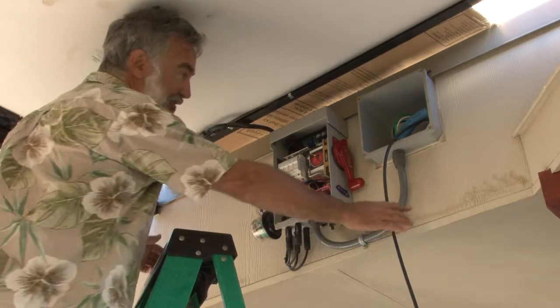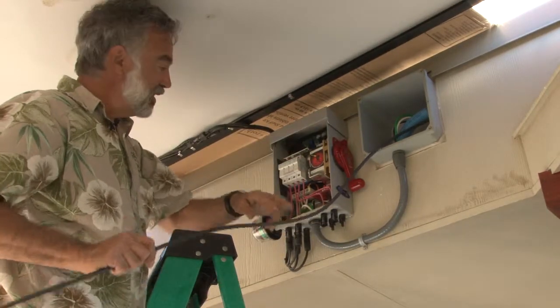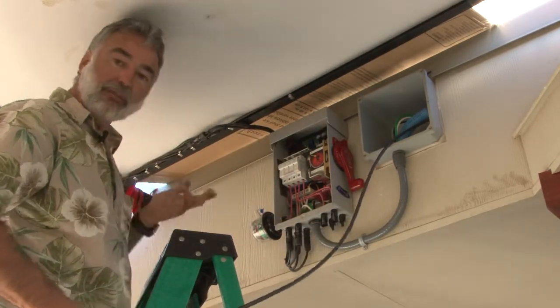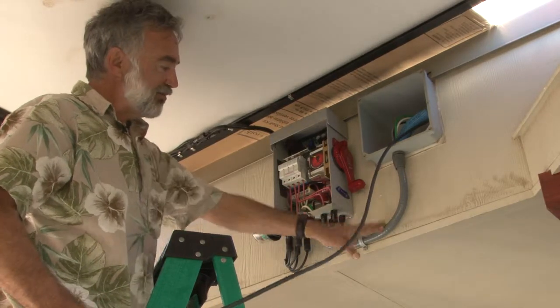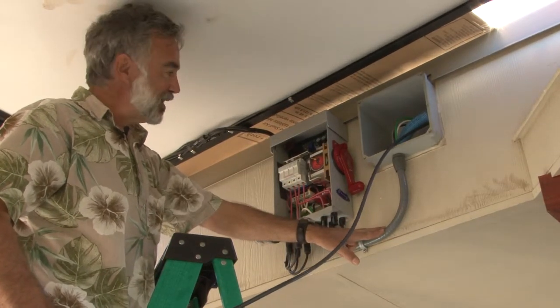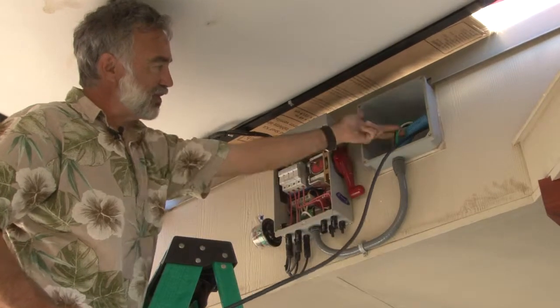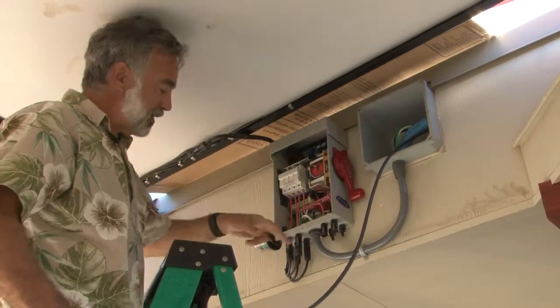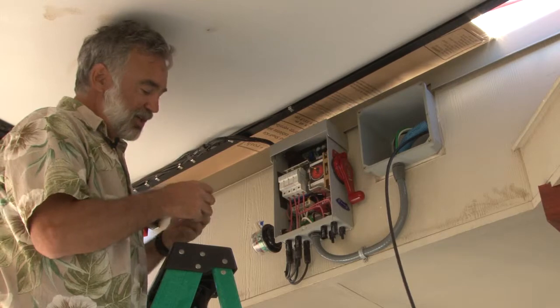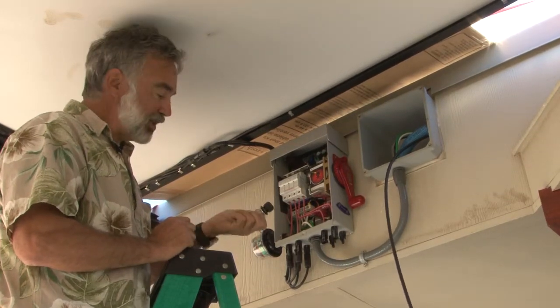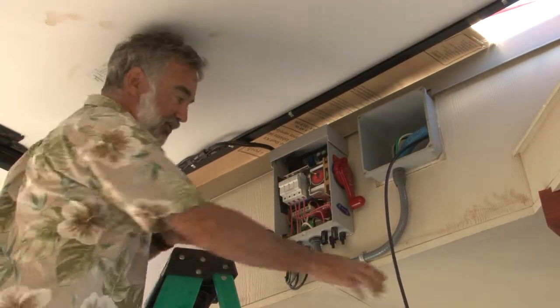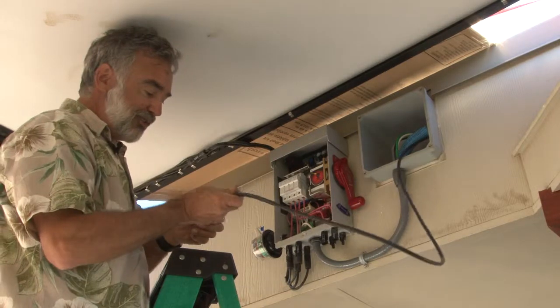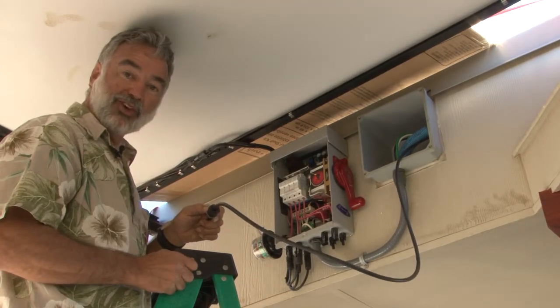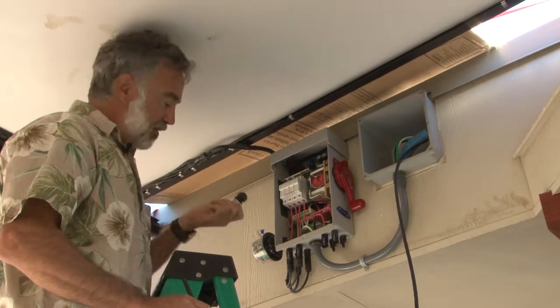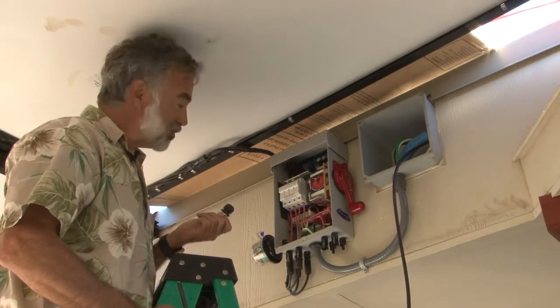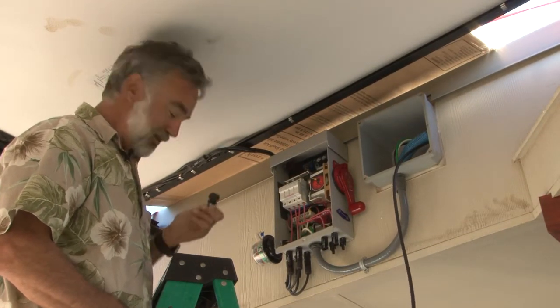Okay, we've got our Cat 5 cable up here into our pull box, and we've got to get it into our combiner box. There's a couple ways we could do this. If we had a larger conduit here, say 3/4 or 1 inch, we could simply run it right in with the high voltage cabling to get it across. But since the Birdhouse comes with two watertight 1/2 inch strain reliefs, conveniently sized for our Cat 5 cable to give you a waterproof entry, we're going to use those, both because we've got them and because we're too lazy to change the conduit out at this point.